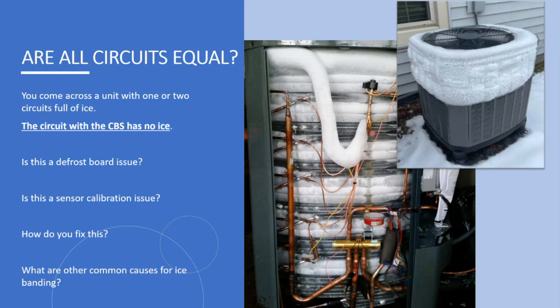But when you see banding like this, often that's going to be charge related, where low charge can cause banding in a lot of cases. So look for how even it is. If you see it building up from the bottom up, that's probably a drainage issue. This one's raised up, so the water that comes off of it has somewhere to go, and the snow isn't building up on the side. But if it's building from the bottom up, that's often a drainage issue.